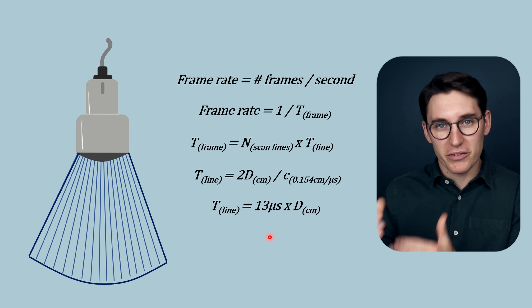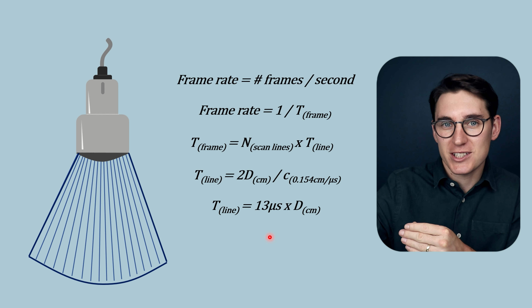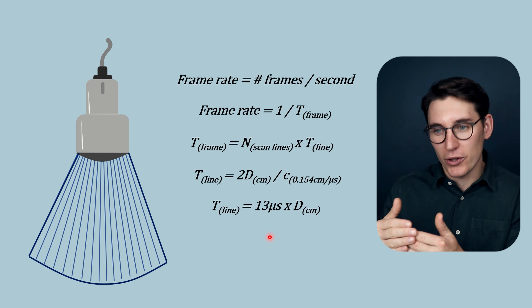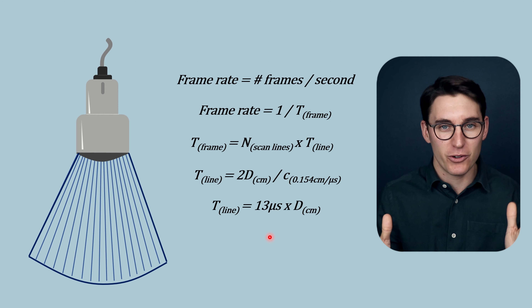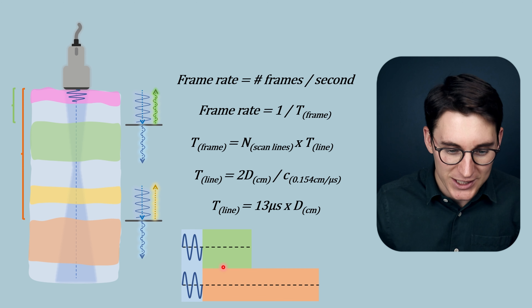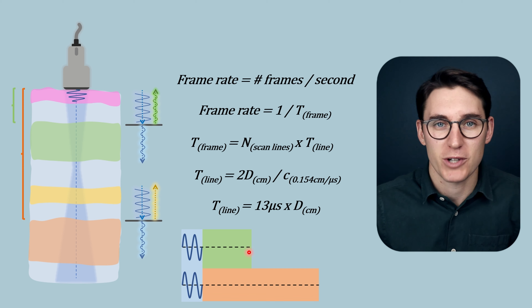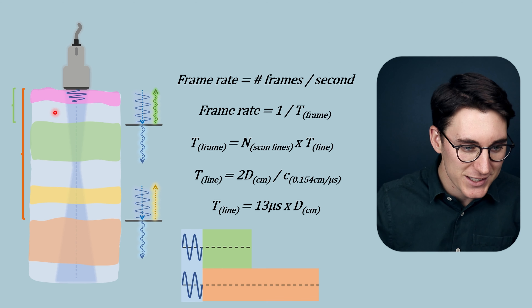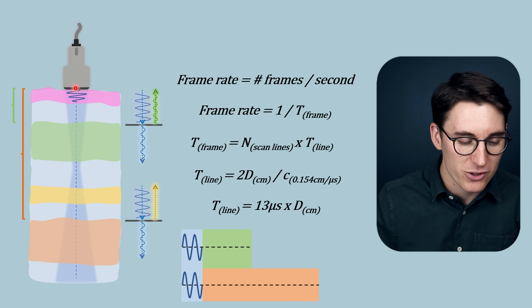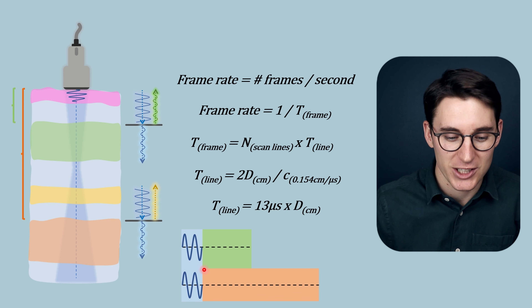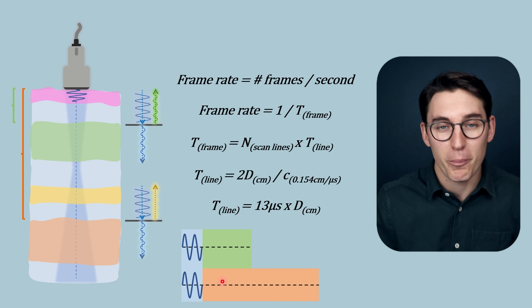What we've calculated is the time it takes for one pulse to travel into the patient's tissues to a specified depth and return back before the next pulse can be released. That's our pulse repetition period — the amount of time between the first pulse and the next pulse in our sequence. The pulse repetition period covers both transmit time and receive time. For shallower depths, the pulse reaches the target and returns much faster, giving a shorter pulse repetition period. For deeper imaging, a longer receive time is required, making the pulse repetition period longer.